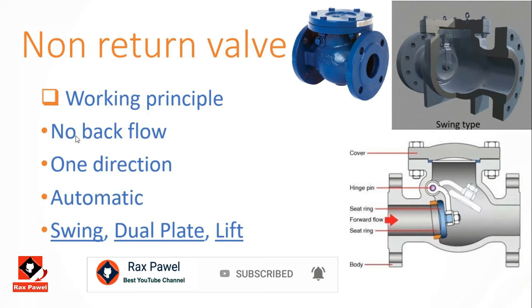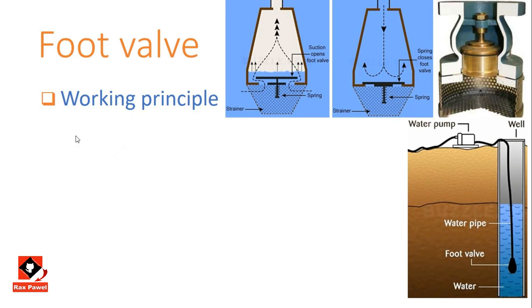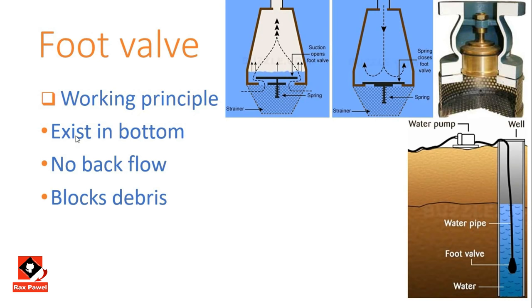Working principle of foot valves: this is also a check valve, used at the bottom of a pipeline. They are typically present when water is being drawn from a below-level water source. The foot valve prevents backflow to ease the suction process and also prevents impurities and debris from entering the pipeline.